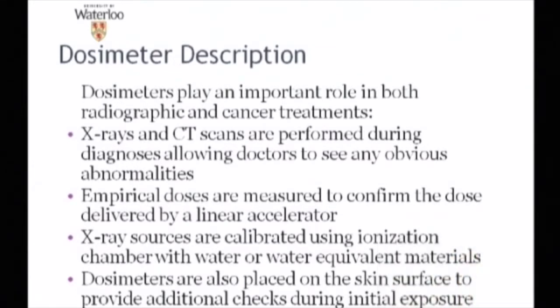So dosimeter description, basically we use every single morning in Cancer Center where we use linear accelerator or X-ray to generate X-rays or E-beam to treat cancerous tissues. We have to characterize the X-ray machine just to make sure that the oncologist prescribe a certain dose to a certain location on the patient's body. We are delivering the correct dosage, as well as delivering it to the correct location. And our application is not just for treatment X-ray, but also for diagnostic X-ray.